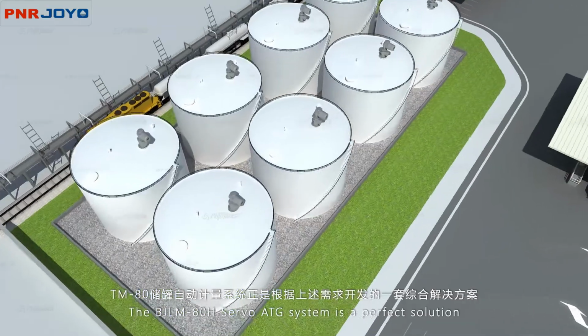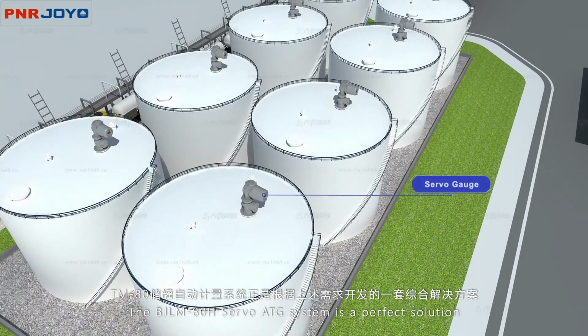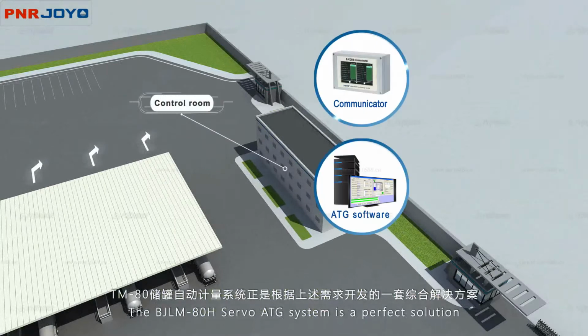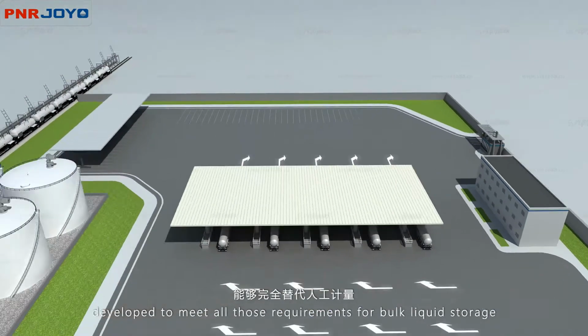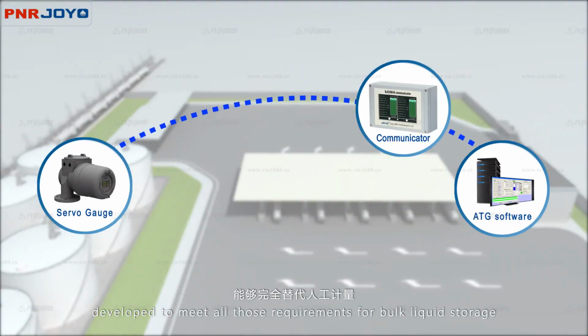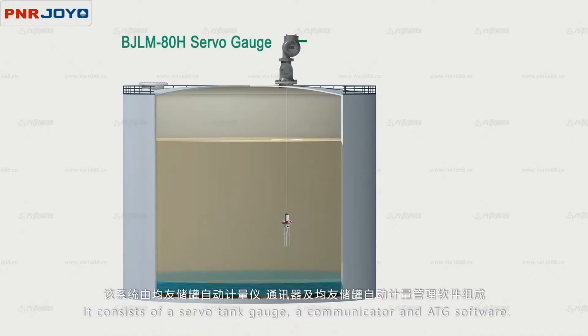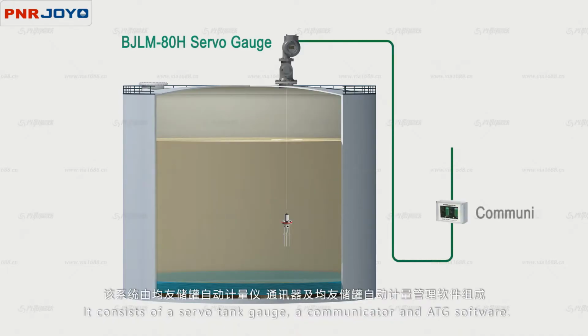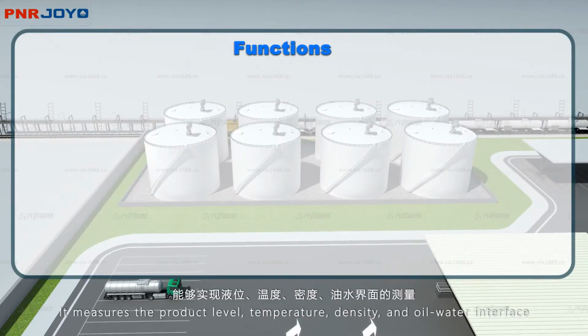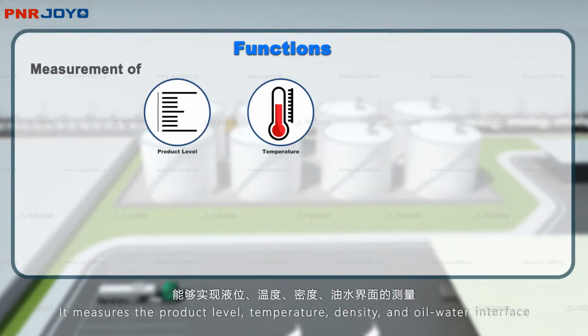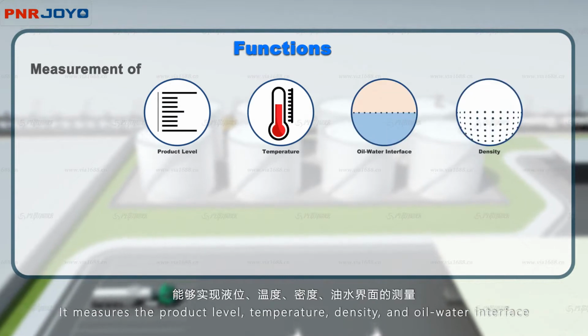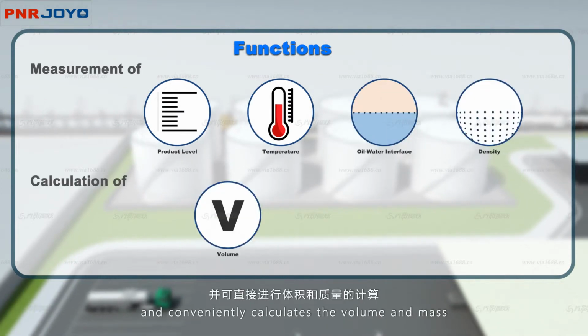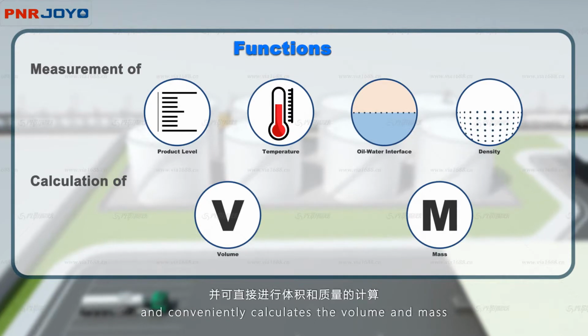The BJLM 80H Servo ATG system is a perfect solution developed to meet all those requirements for bulk liquid storage. It consists of a servo tank gauge, a communicator, and ATG software. It measures the product level, temperature, density, and oil-water interface, and conveniently calculates the volume and mass.